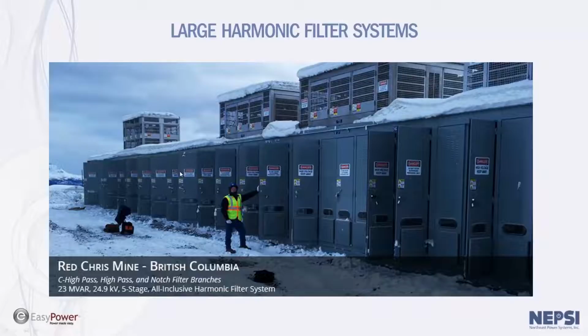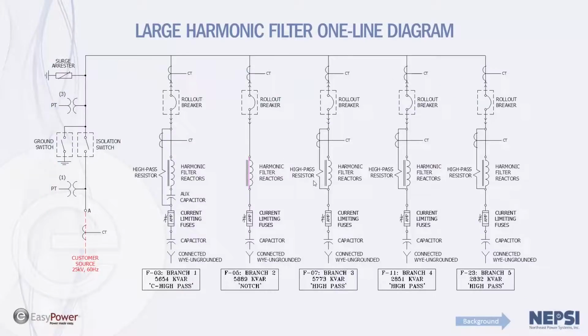Pictured here is a NEPSI metal enclosed harmonic filter system located at the Red Chris mine in British Columbia. It was rated 23 megavars, 24.9 kV, and it's a 5-stage, all-inclusive harmonic filter system. This metal enclosed filter system comes with all switching, all protection, and all control, as noted here in the one-line diagram for that product offering.